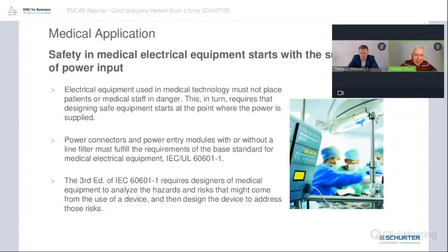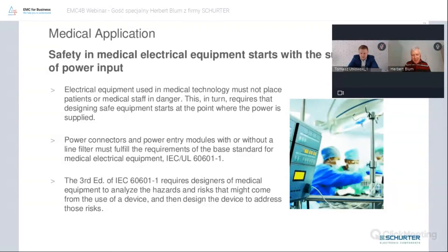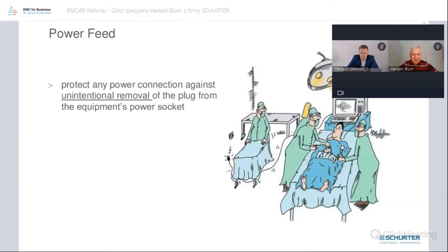The main standard here of course is the IEC 60601-1, which is the basic standard for medical applications. The good thing is it is also harmonized with the UL standard.